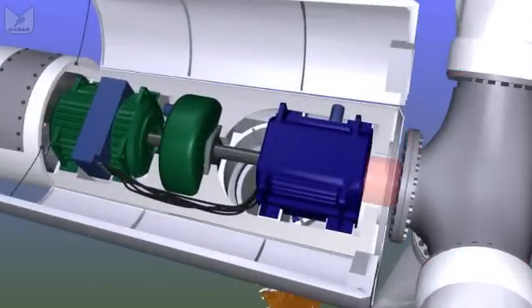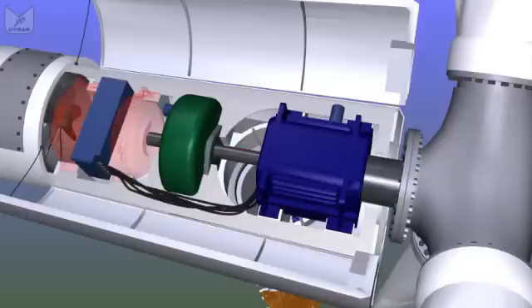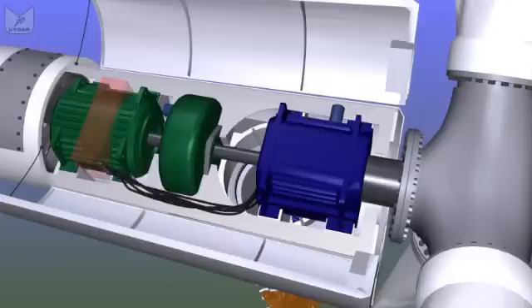Out of the back of the hub, we have a shaft, which leads into the gearbox, then a high-speed shaft, through a brake, into a generator. And that generator then supplies the electrical power, as they say, at about 690 volts, all the way back down the tower to the base.